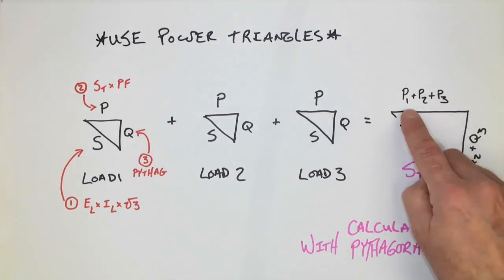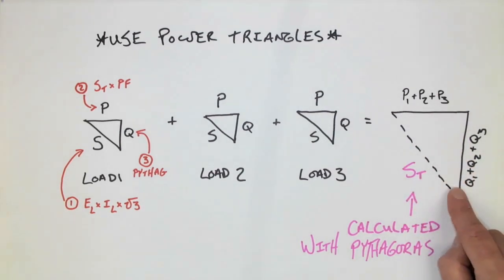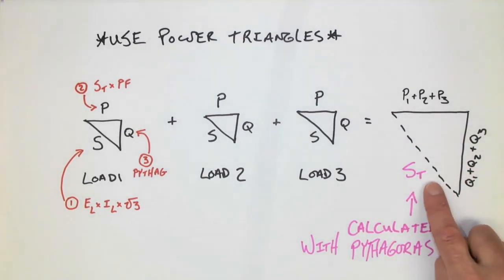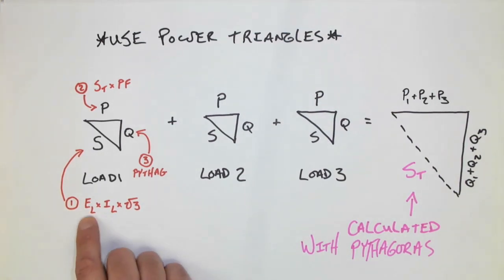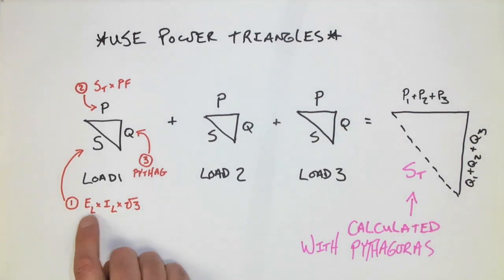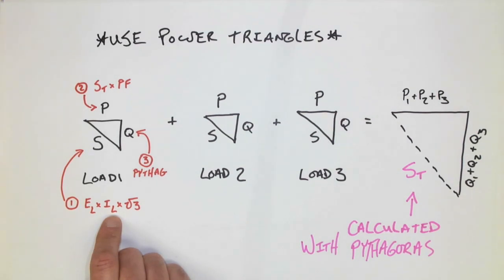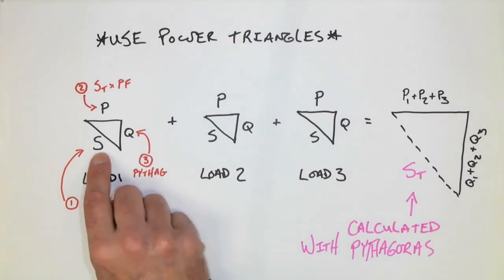After I've added the totals, I will then calculate the total VA for the circuit by using Pythagoras. Most questions will give us a voltage of the source and a current for the load. If I use the voltage line value and current line value times root three, I automatically get the S.